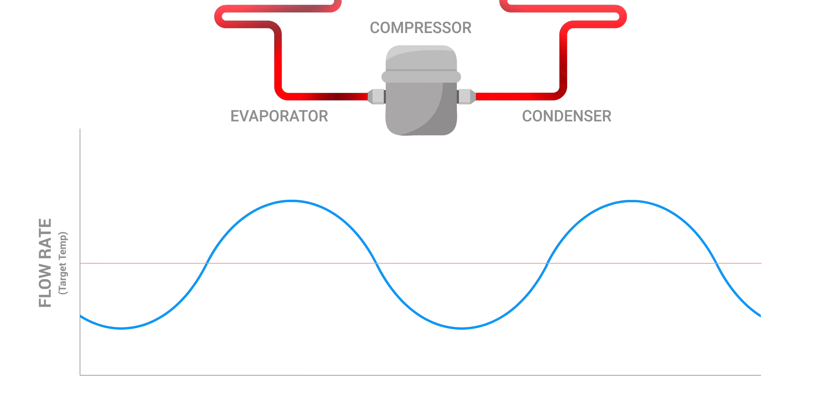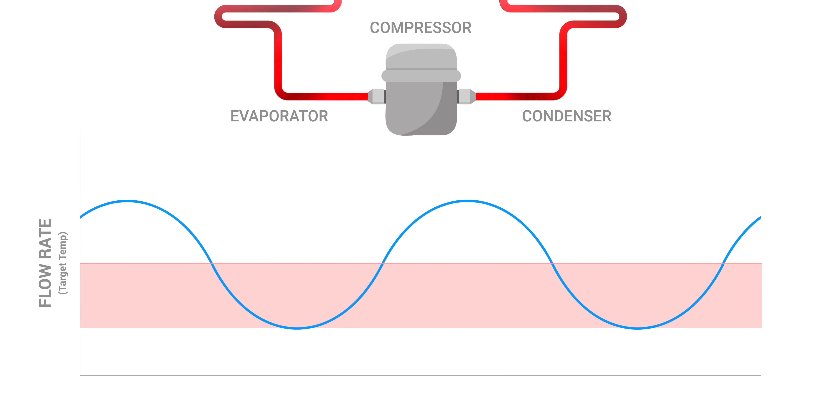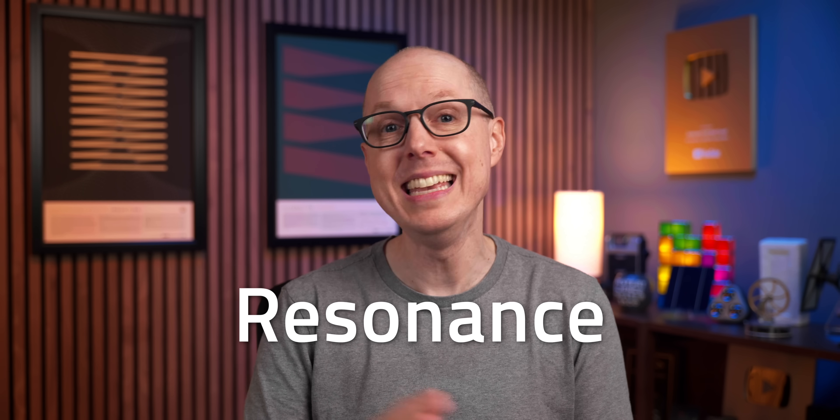So what's so bad about that? There's a space in the lower part of the sine wave where conditions are right for liquid to start forming in the compressor. Once again, that would be bye-bye compressor. As so often happens in engineering, this creates a cascading problem. If your system isn't well optimized, it's going to overshoot the working fluid's happy place by a lot, creating greater oscillations or waves and more chances for fluid to build up. Even worse, this oscillation can build — called resonance — meaning the overshoot and undershoot can become larger with each cycle, and every heat pump has to deal with this issue.